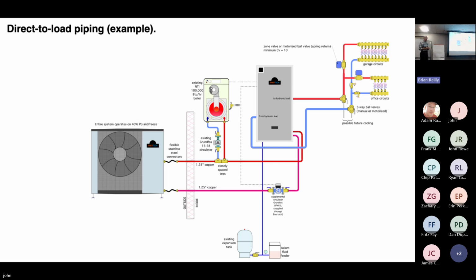So that's where we put the buffer tank in. The one Achilles heel with this is that it needs something to tell it to turn the compressor on. Normally, if you have zone valves, they have an end switch, and the end switch closes when the zone valve opens. That end switch closure is the signal, hey, something's calling for heat, turn on the heat pump. But with thermostatic valves, you don't have end switches. So that's one drawback with that.